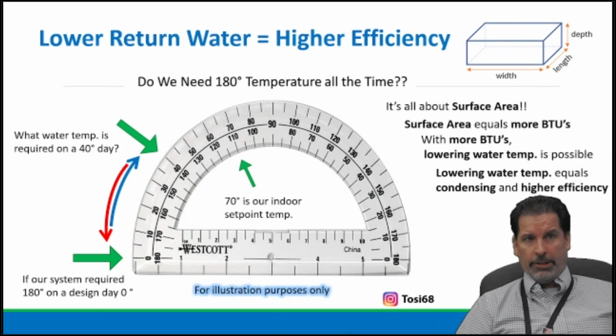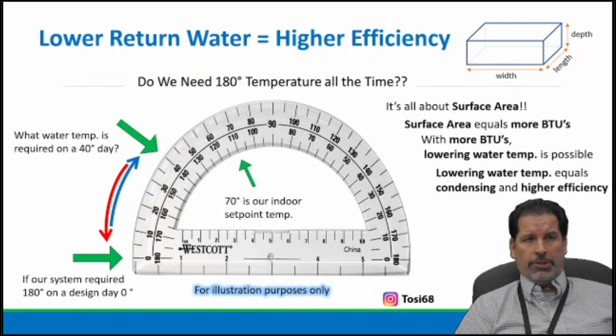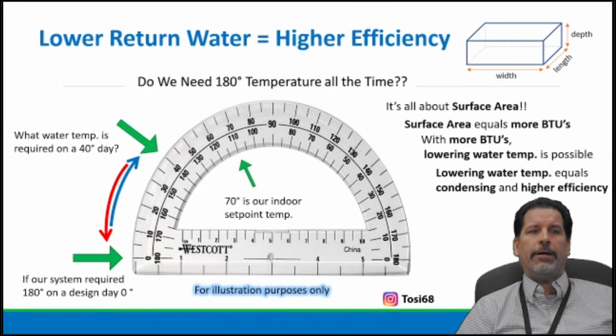That's where the technology in the firmware, the software, and these microprocessors that we're not even taking advantage of. People aren't even hooking up outdoor sensors, telling the machine that it isn't 0 out. So the thing is always firing 180 degrees regardless. Overheating can be an uncomfortable situation as well. I don't know what you plan on doing, taking your tin snips out and removing some fins off a baseboard, but understanding lowering water temperature is where you want to be.